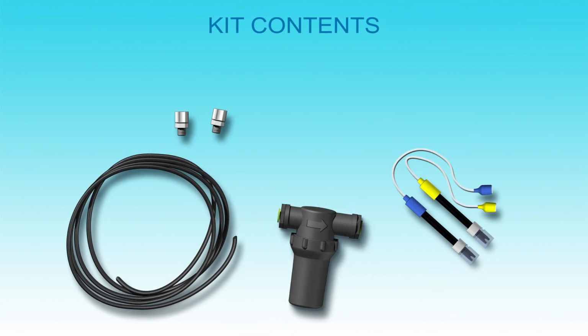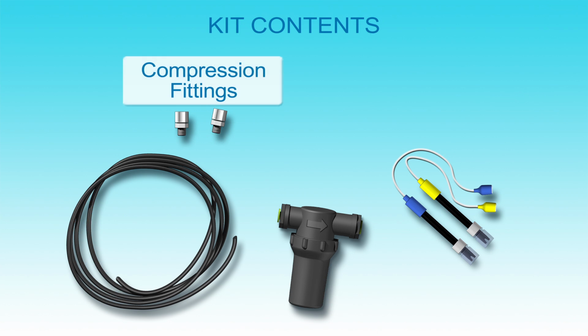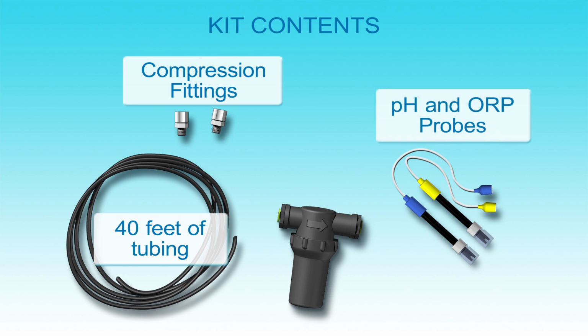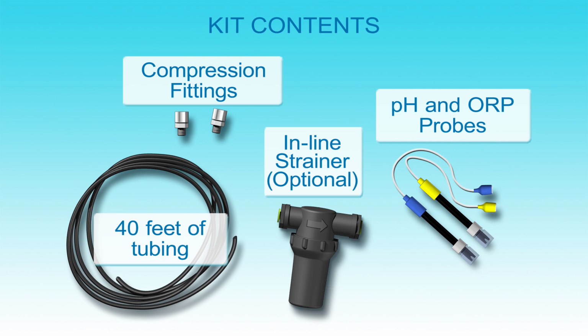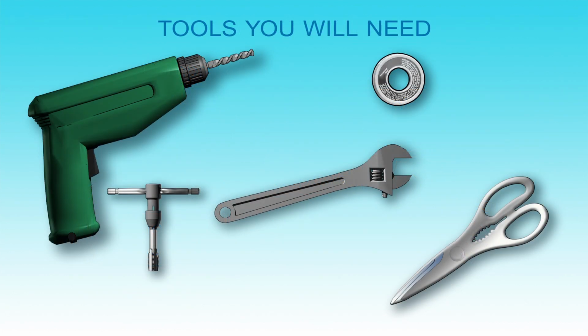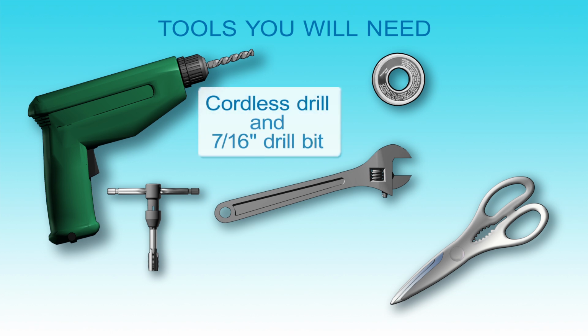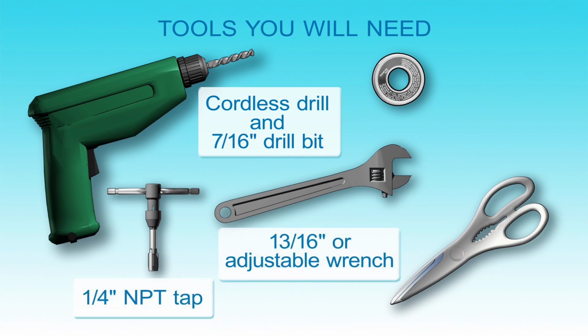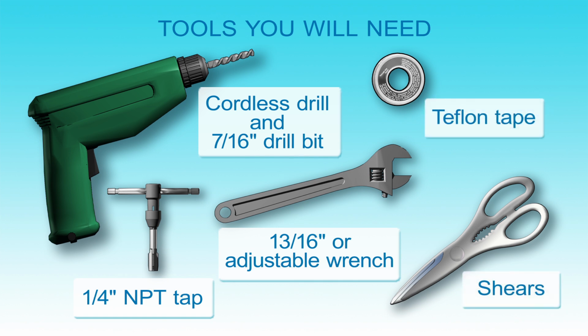The kit also includes 2 compression fittings, 40 feet of 3/8-inch tubing, and the pH and ORP probes. Your kit may also include an inline strainer. To install the controller, you will need a cordless drill, a 7/16-inch drill bit, a 1/4-inch NPT tap, an adjustable wrench, Teflon tape, shears, and appropriate fasteners to mount the controller securely.